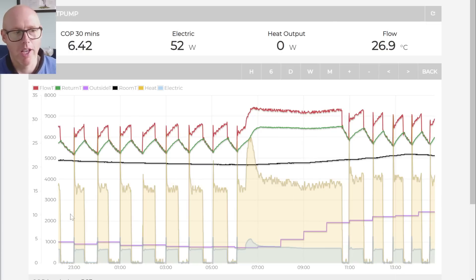This goes to show that cycling is normal. Short cycling isn't great, but this example is just so perfect: at an outside temperature of 3 degrees, the heat pump ran from 6am way past 10am on a single cycle — hours and hours on one cycle. This is a well-sized heat pump. Unfortunately not all the heat pumps on Heat Pump Monitor look like this, and every time you cycle you are leaving some efficiency on the table. In milder weather you will see much more frequent cycling, and those shoulder months are where you'll really suffer with a grossly oversized heat pump.